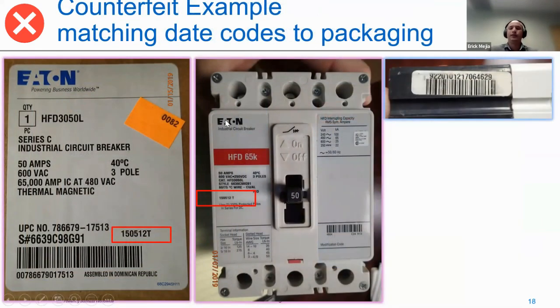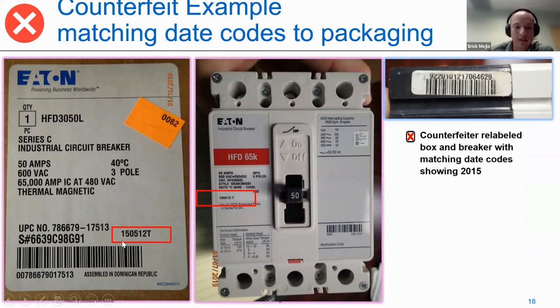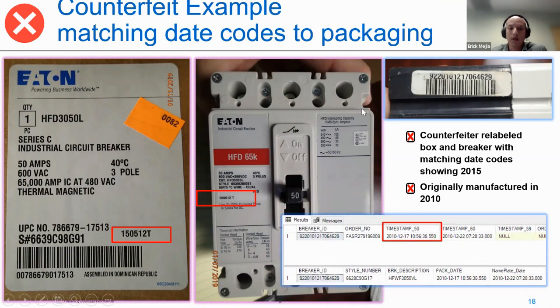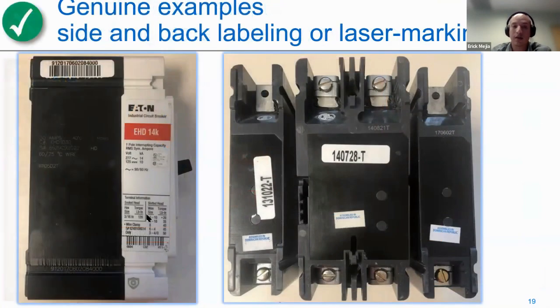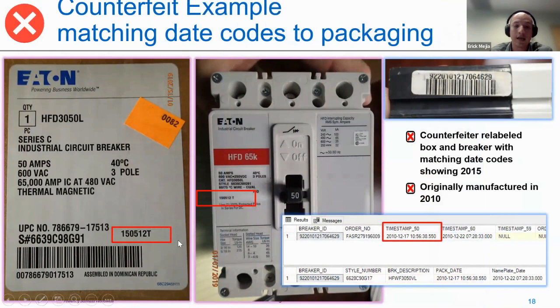When I was talking about the dates and the labeling, I was referring to these numbers you see here. In the initial picture of the 5 circuit breakers, one did not have the printing of when it was manufactured. When you have a counterfeit, you have to check the labeling on the carton, on the packaging, then the labeling on the breaker itself, and then the labeling on the side of the breaker as well.